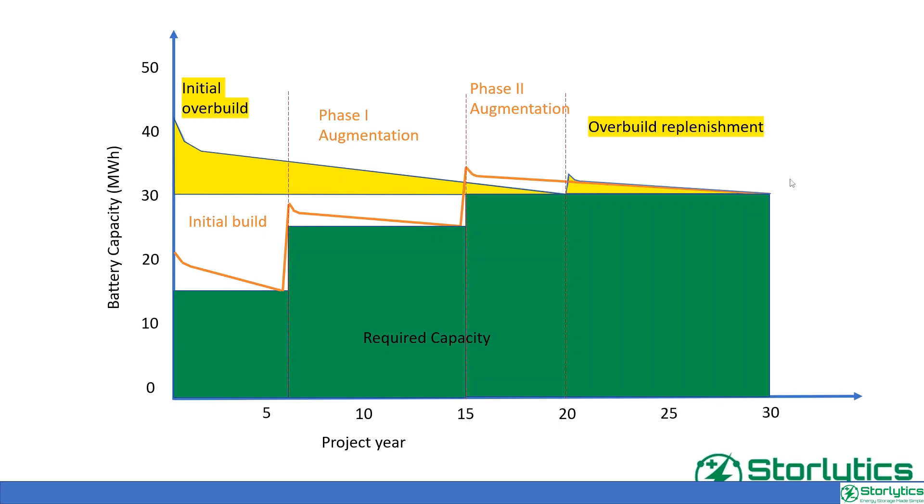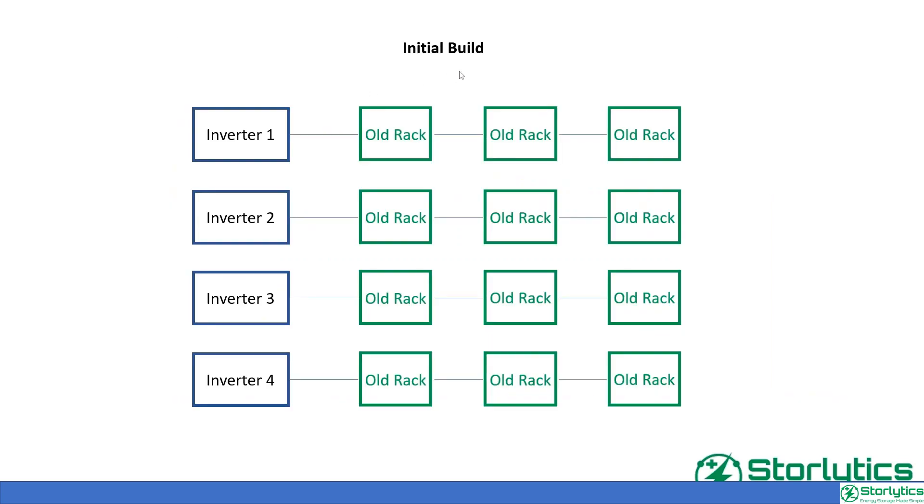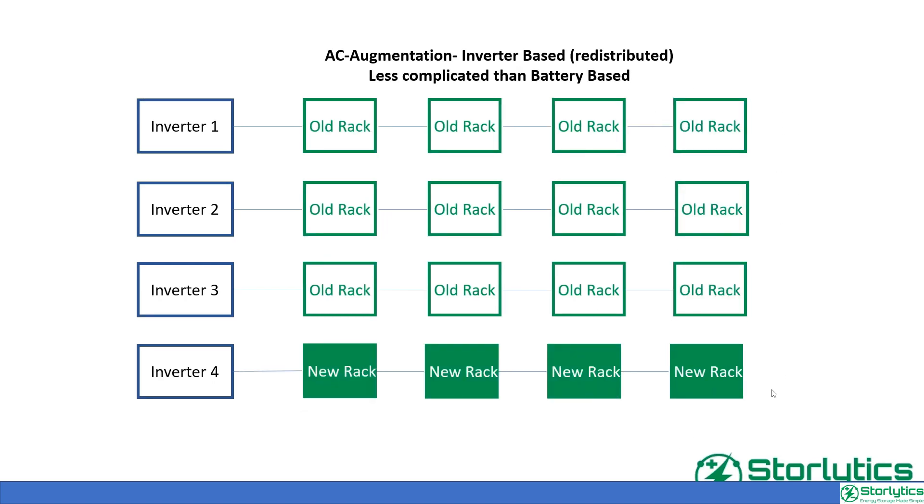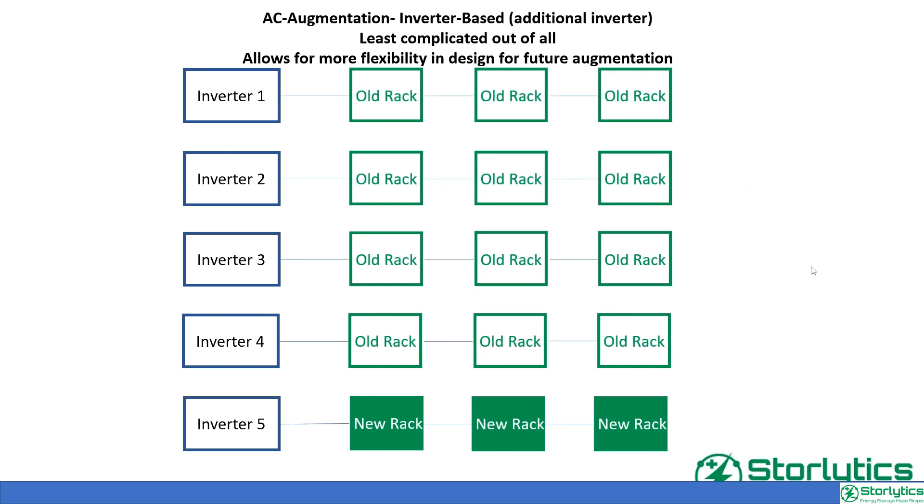In DC augmentation, a new battery rack is installed behind an existing inverter, parallel to the older battery racks. In another format, the older battery racks can be redistributed and all the new racks can be installed behind one inverter. Whereas in AC augmentation, a new inverter battery system is added to the existing fleet of inverter battery units. AC and DC augmentation in battery energy storage systems have different design approaches and applications.